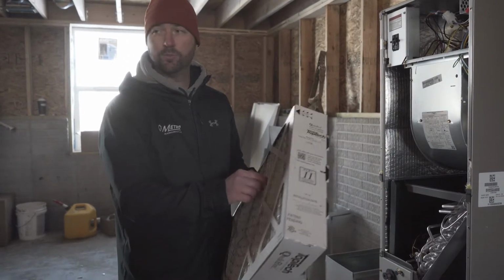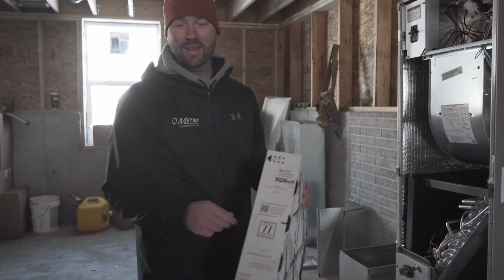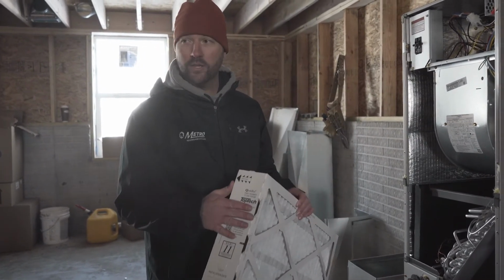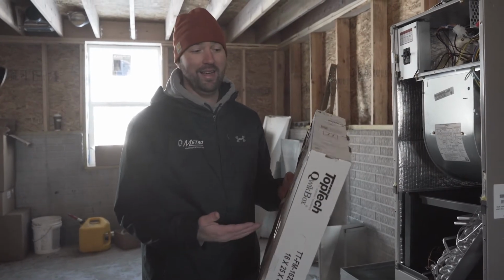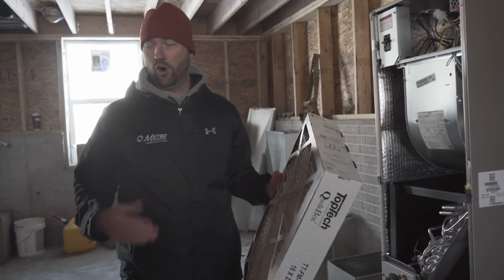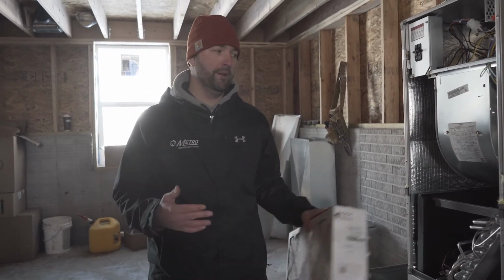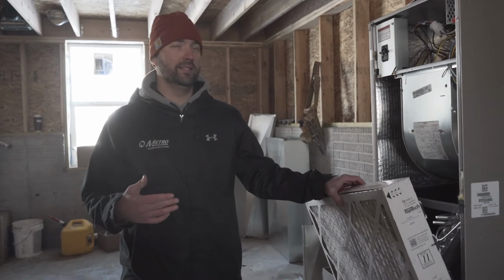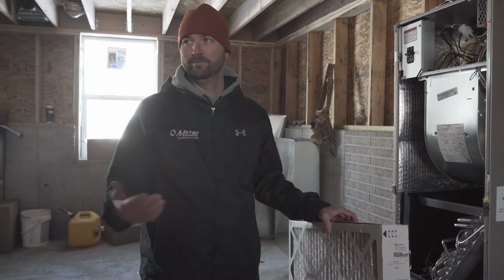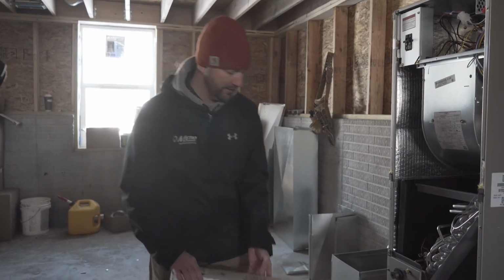When they have the 1-inch pleated filters, those are actually bad for your furnace, so if you're using those, stop. Get the cheaper ones that you can see right through, and then change them once a month. These 4-inch filters though, because of the surface area, they can last anywhere from 6 months to a year. Just because they're oversized and they just last that much longer. The filter itself could handle more than what this blower can push. So the bigger the blower, the more surface area that you want. If that makes sense.